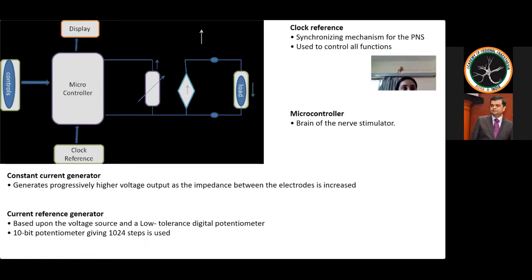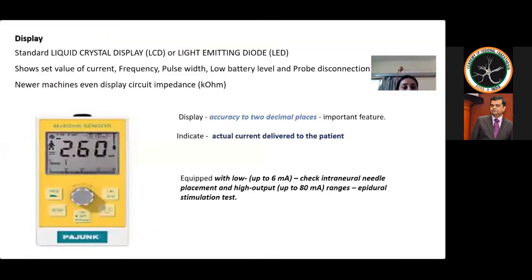Then we have the current reference generator. It is based upon the voltage and a low tolerance digital potentiometer. Now it changes resistance over its entire range, and it is controlled by a microcontroller. It uses a series of commands which tell it to increase or decrease the value. So a 10-bit potentiometer giving 1024 steps is sufficient for the application. Now the display, which is LCD or LED in type, shows the set value of current, frequency, pulse width, and low battery level and probe disconnection. In newer machines, it also displays the circuit impedance in kilo ohms.